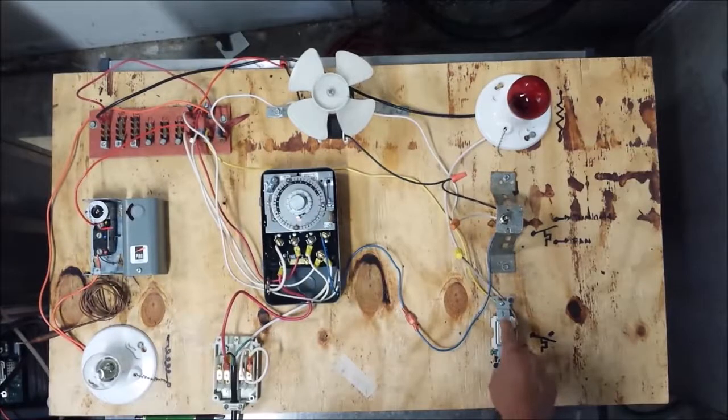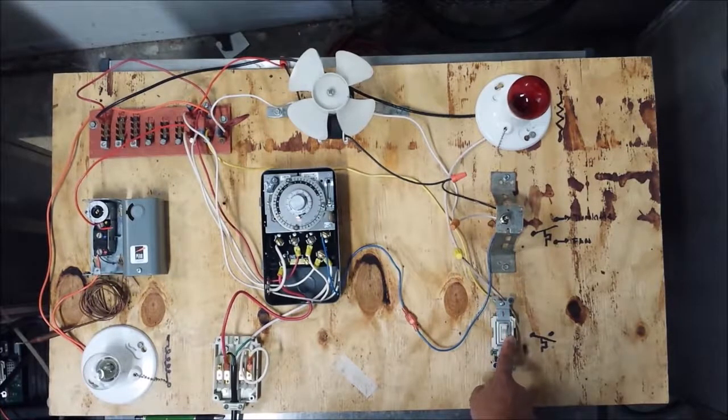And then here we have a little light switch. This is basically representing a thermostat, and if the temperature rises to the point where it gets too hot, it's going to kill whatever it's in series with. So this here is our heater limit switch. If the heaters get stuck on for any reason, the temperature of that thermostat starts to increase, and when it opens, it's going to kill the heaters as a safety precaution.